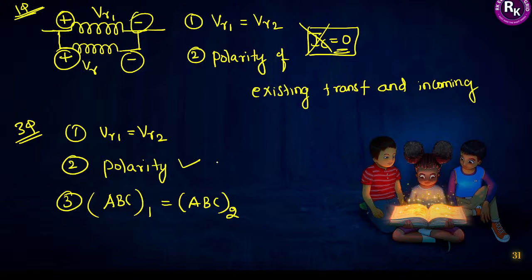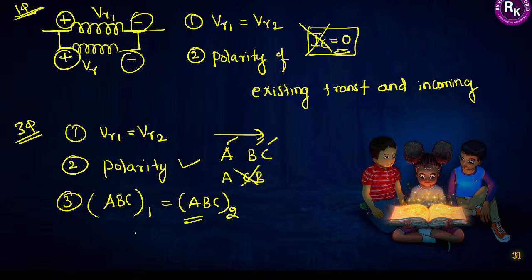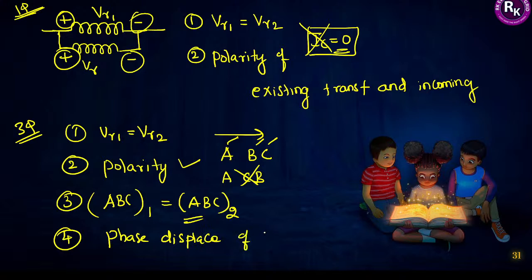If the existing transformer is operated in the sequence ABC, you must bring the incoming transformer in the same order — A, B, C. The fourth mandatory condition is that the phase displacement on the secondary side should be zero. The difference between the phase displacement of the existing transformer and the incoming transformer must be zero.